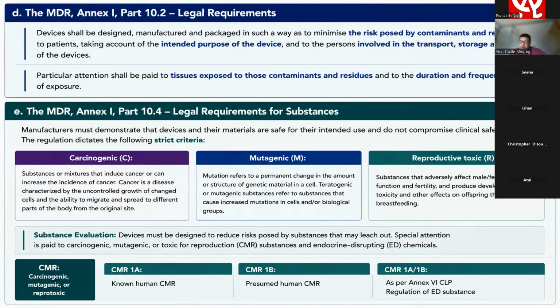So the alternative is to remove that substance: you must manufacture your device so that it may be DEHP free. Again, if you want to manufacture your device with DEHP, that is, with the presence of the phthalate, you must keep it within the limit. That means we need to understand the formula of your tubings and drip chambers. So if the overall weight of my device is 14 grams, then it should be less than 0.1% of the 14 grams. That is the dioctyl phthalate.